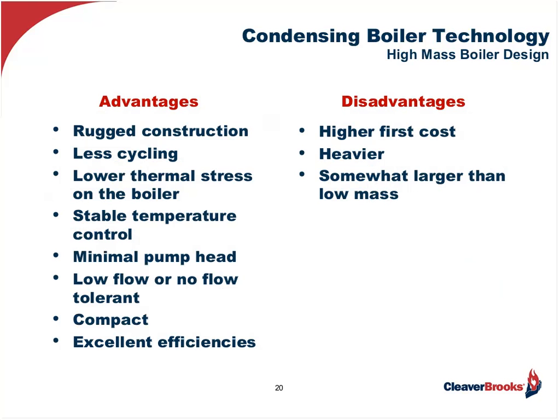And one of the most important things is they're very tolerant to low flow, and in fact, most of them can live with absolutely no flow, which makes them ideal for variable flow primary pumping. And compared to conventional boilers, they're compact. The disadvantages are they do have slightly more material, so they're going to cost a little bit more. They're a little bit heavier, and they're somewhat larger than the low mass boilers.